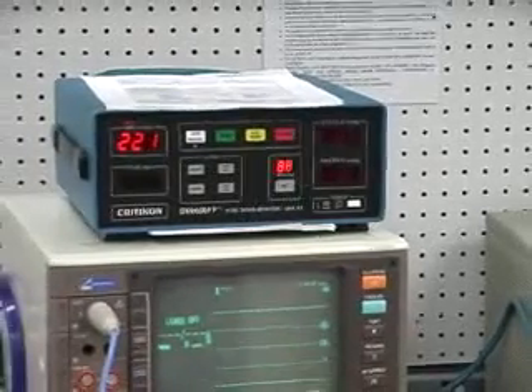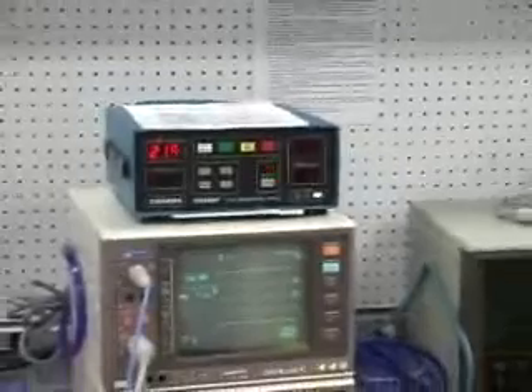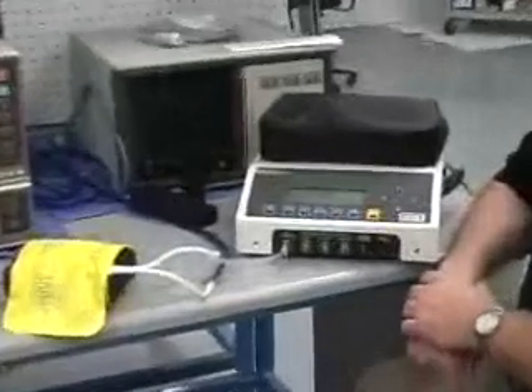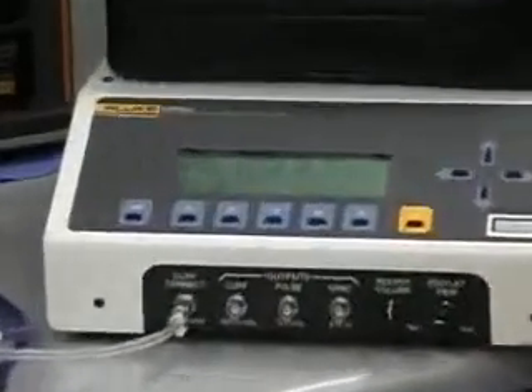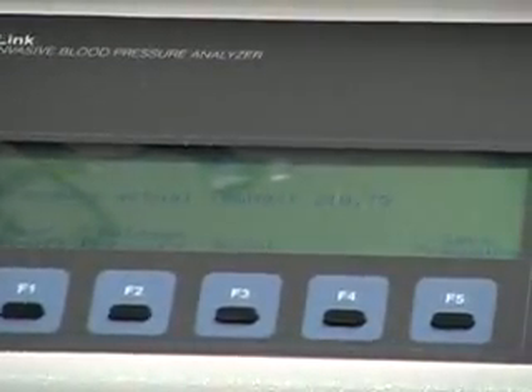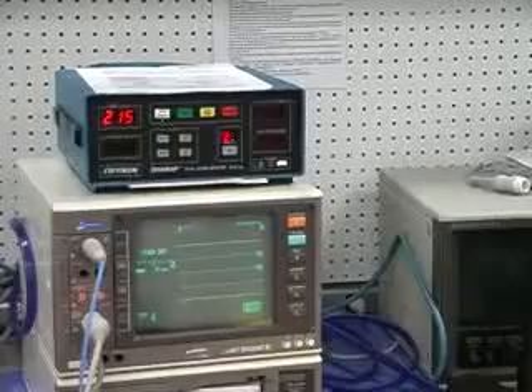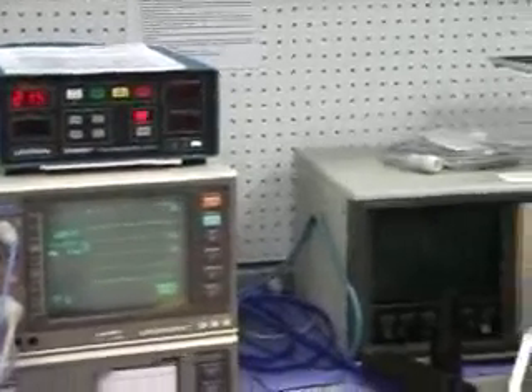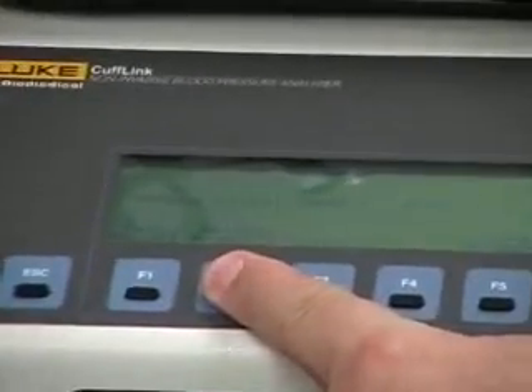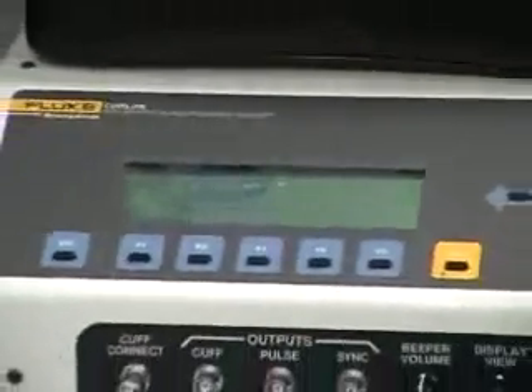And we read about 215, 214 on the Cufflink, 218 on the Critikon. And so it's just a verification that the transducer is calibrated rather well. And I guess if you wanted to, you could do a more calibration adjustment on that, but for purposes of this demonstration, it's adequate. Now we can go in, release the pressure, open up the line, goes back to 0. Then we escape out of the manometer test.